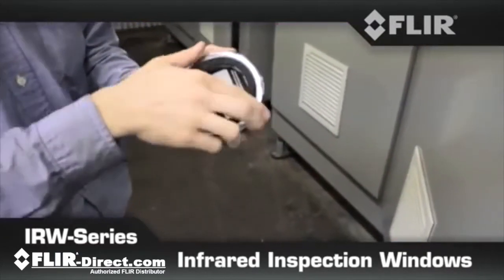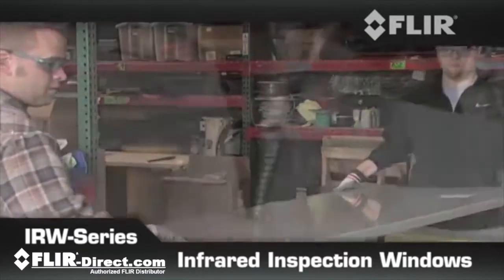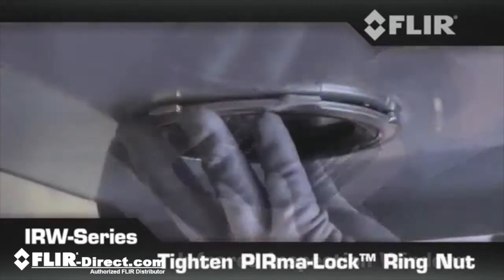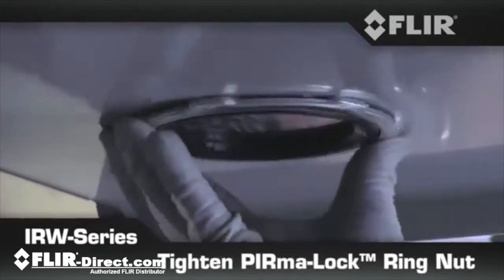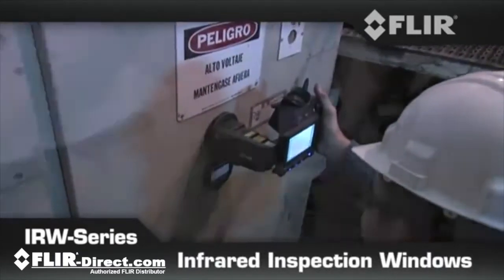FLIR IR windows are not only the easiest to use, they're also the simplest to install. Knock out one hole with a standard punch kit, insert the FLIR IR window assembly, and secure it with FLIR's unique self-grounding PIRma-Lock ring nut that bonds tight. In no time, you'll be back up and ready.